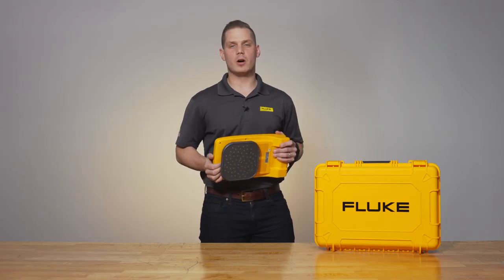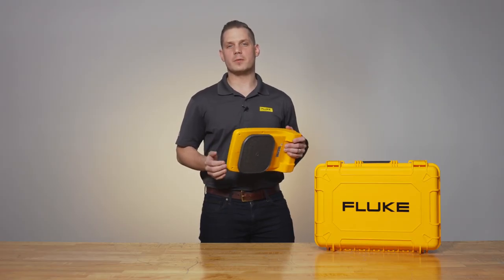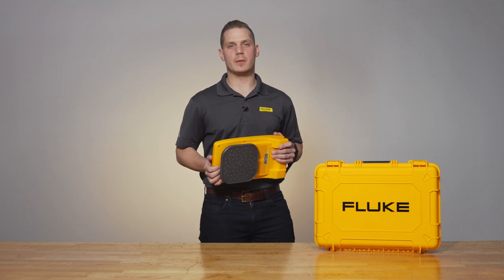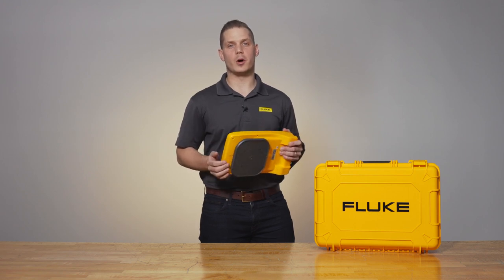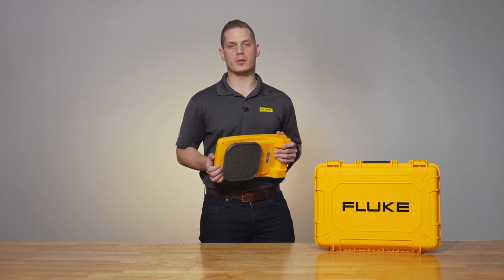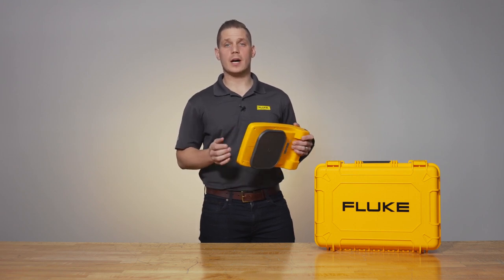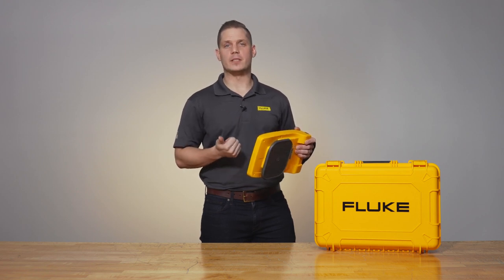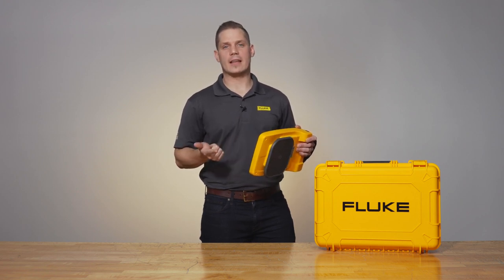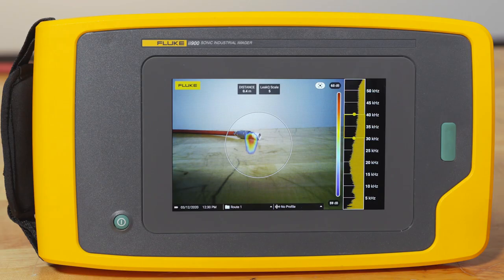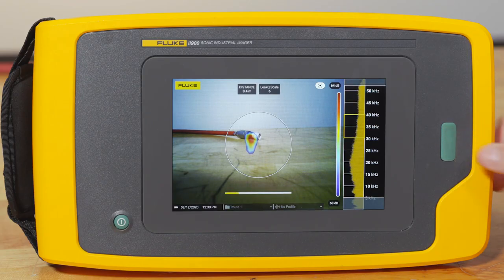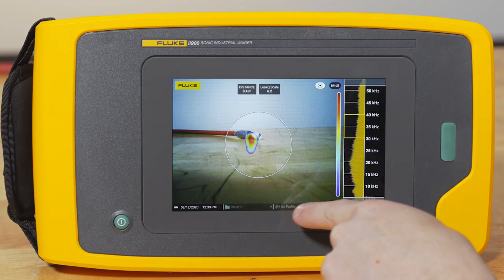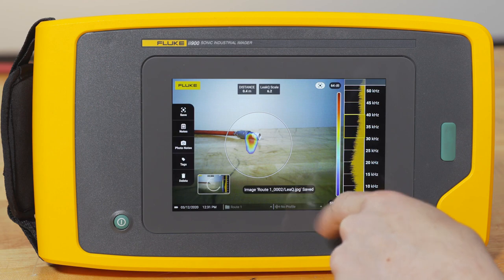Capturing images in LeakQ mode is a little bit different than capturing images in image mode or video mode with the ii900. Once you've got the leak positioned in the center of the screen and you've got both the distance and the LeakQ severity scale populated, you're going to want to push and hold the green button and hold the camera fixed on that leak for one and a half seconds.